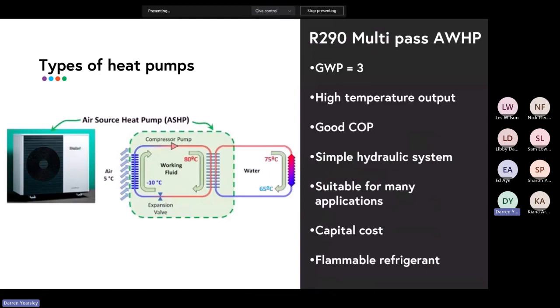And the COP across the appliance is very consistent. So the duty cycle of your hot water system doesn't affect the COP greatly. The only things that really affect the COP is what's my primary flow and what's my outdoor air temperature. So to create a model for the performance of the system is now much cleaner and much more consistent. And the heat pump also does very well under partial load. So you do not need any electric element in the system for operation, only for redundancy if you want that. So recovering ring main losses, things like that, an R290 system does absolutely no problem.